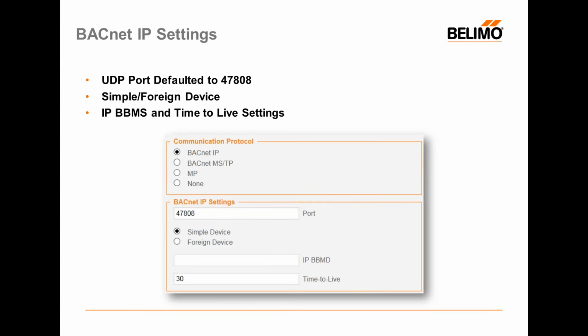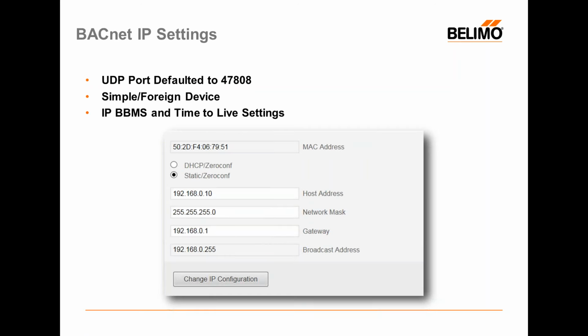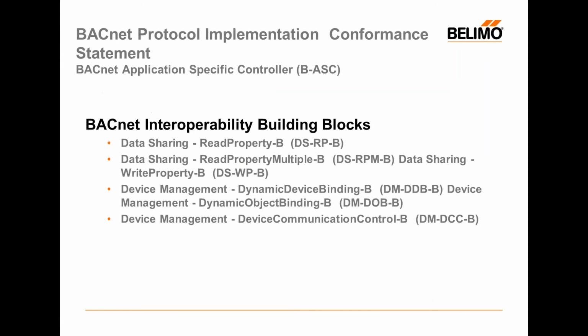The BACnet IP settings are on the same page, and here you would just select BACnet over IP as opposed to MSTP. Our UDP port is going to default to 47808. You can select whether it's a simple foreign device, and if so, you can put in the IP address of the BACnet broadcast management device and the time to live associated with that device. Our IP settings are pretty standard. You'd go to the IP settings page, put in your host address, network mask, and gateway, and select Change IP Configuration. Of course, you will select whether it's a static or a dynamic hosted IP address as well.